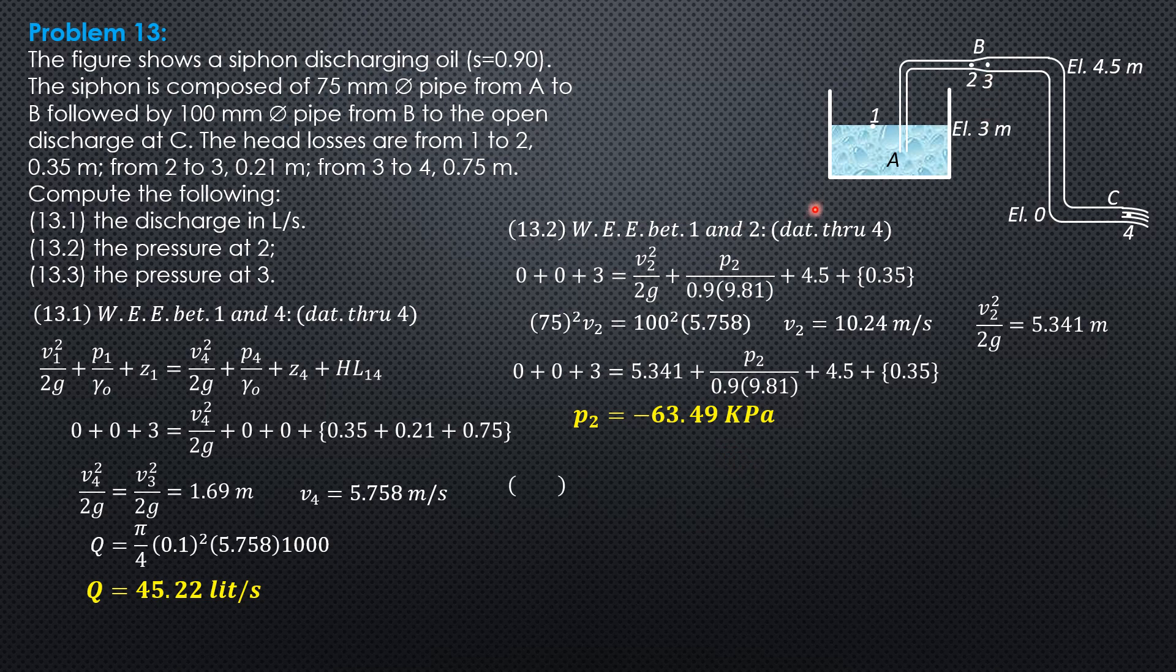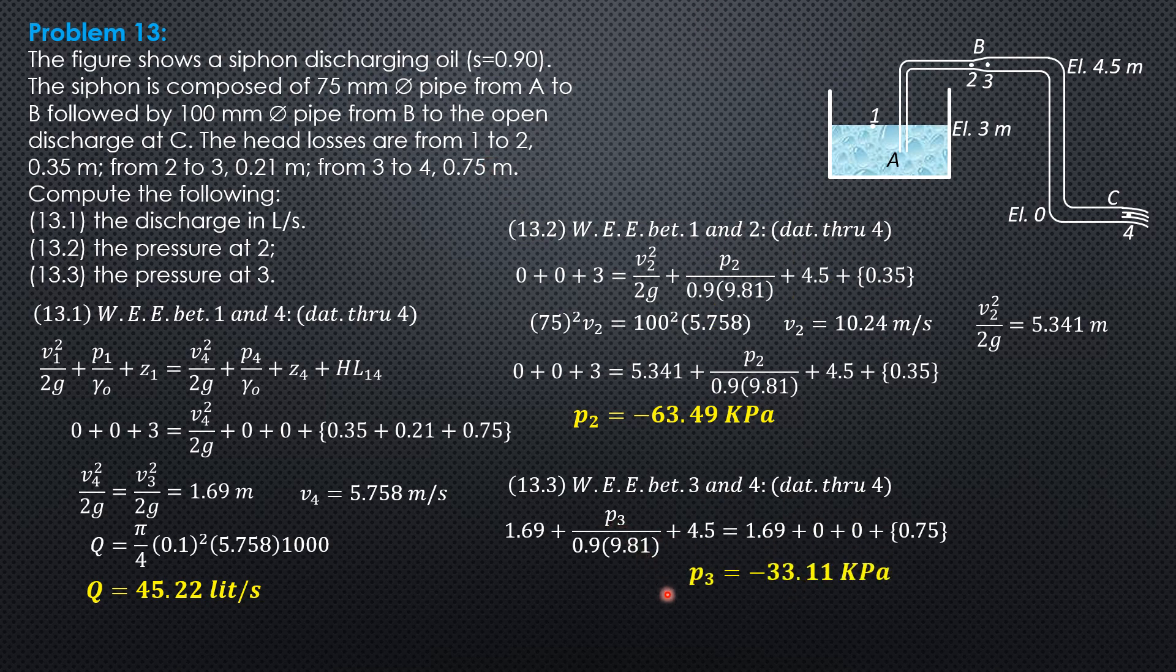For the pressure at 3, we write energy equation between 3 and 4. You can also write 1 to 2 or 2 to 3, but for convenience, 3 to 4. We have velocity head at 3, which is 1.69m, pressure head unknown (P3 over 0.9 times 9.81), elevation head 4.5 equals velocity head at 4, also 1.69m, pressure head 0, elevation head 0, head loss from 3 to 4 is 0.75m. Solving for P3, P3 is -33.1 kilopascals.